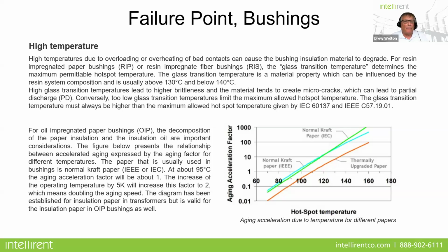So high glass transition temperatures lead to higher brittleness in the material, and it tends to create little micro cracks, which can lead to partial discharge. So lower glass transition temperatures limit the maximum allowed hotspot temperature. We can see here in the graph the aging acceleration factor, and we're talking about normal kraft paper right here. In terms of the aging acceleration factor, this is not life expectancy. This is the acceleration factor of the aging, and the hotspot temperature has a distinct correlation to it as well.